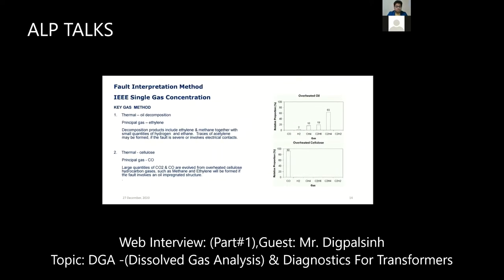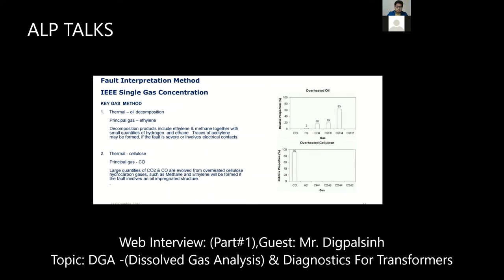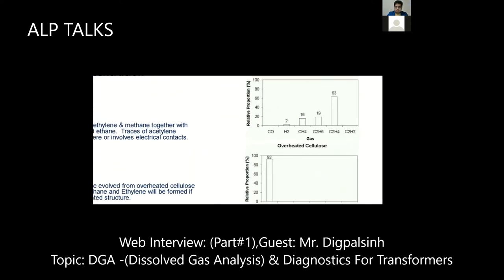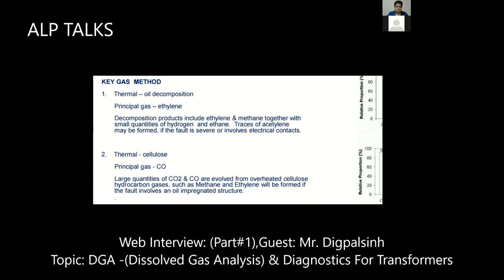IEEE has defined single gas concentrations. So first, in the graph, you can see that if you find only C2H4, which stands for ethylene, in your transformer oil at the time of DGA, then you can say it is a thermal fault. A common thermal fault, but it is not categorized as T1, T2, or T3. It is just defined as a T, thermal fault, and the principal gas for this thermal fault is ethylene.